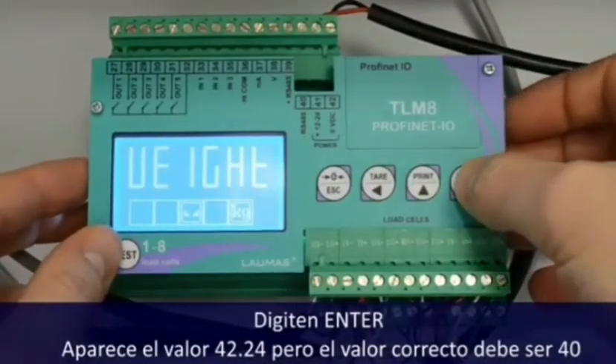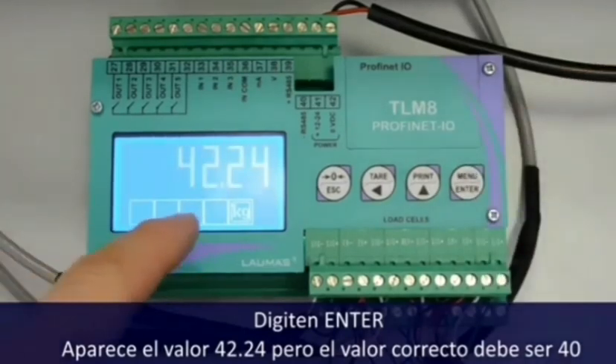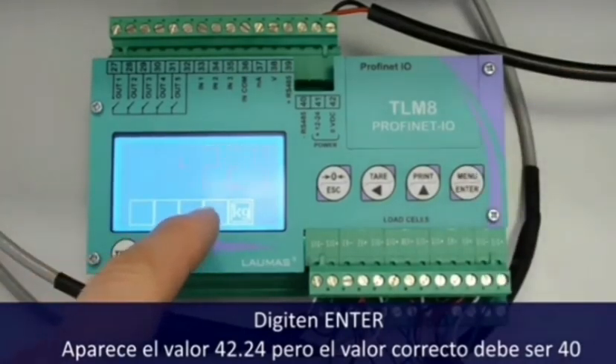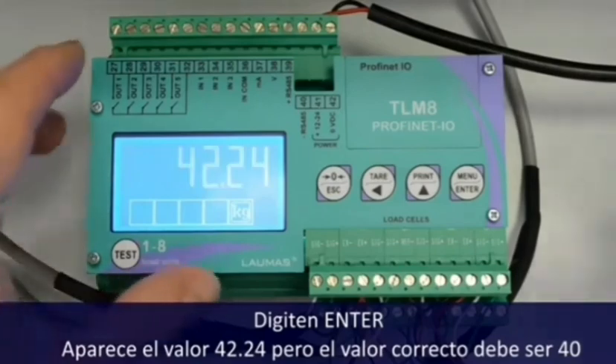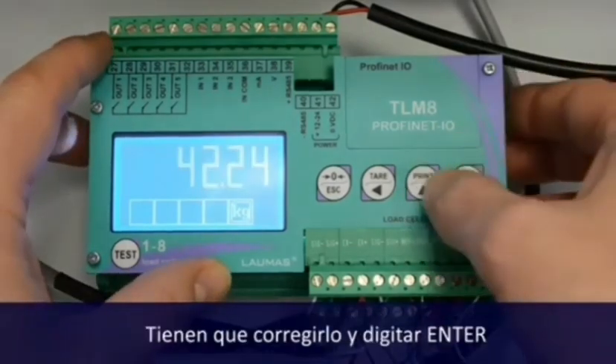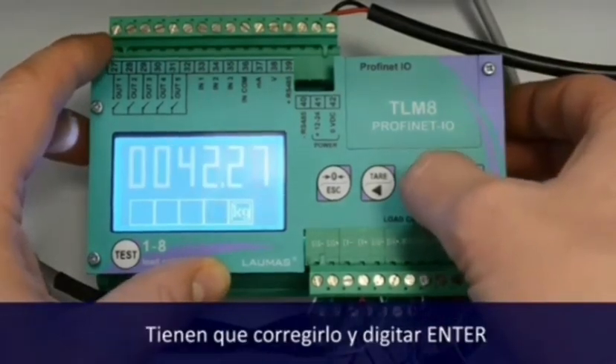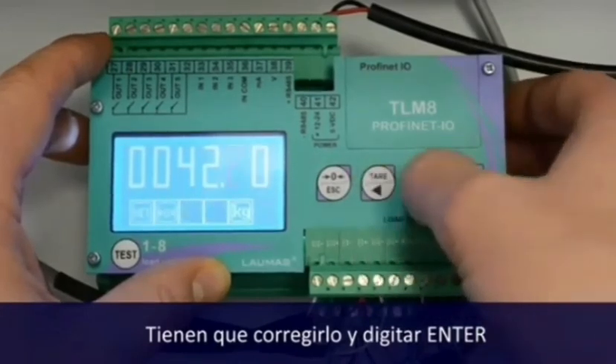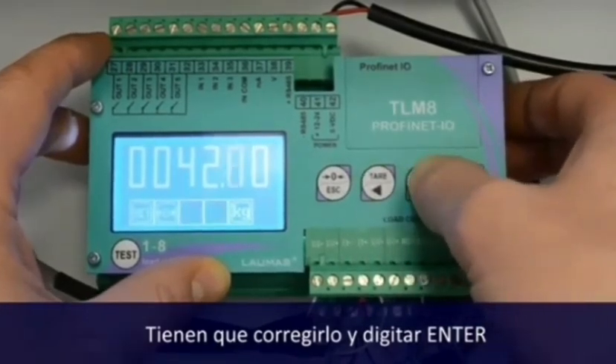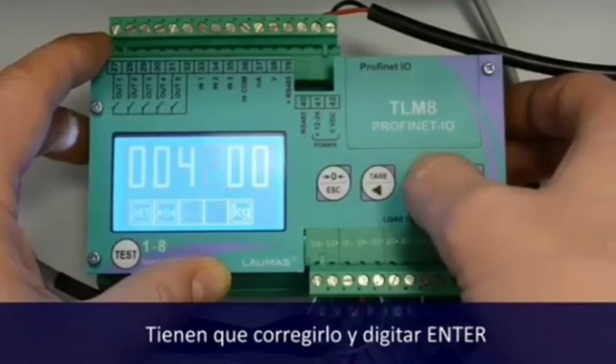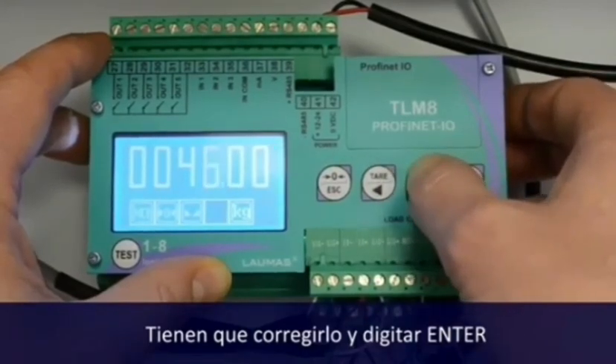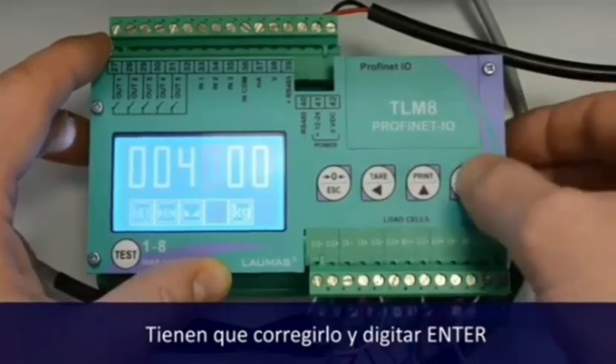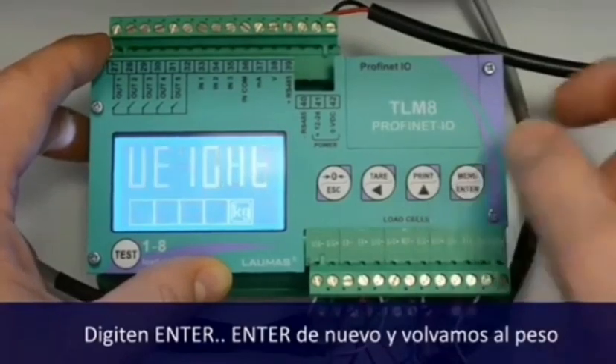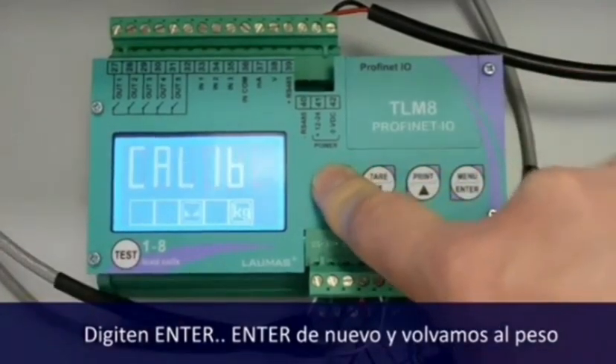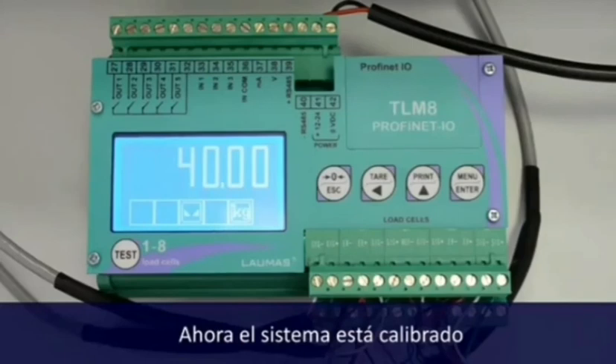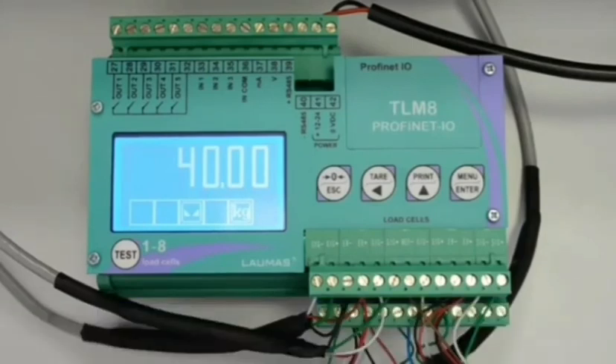Okay, press enter. You see 42 dot something, but we know it must be 40, and so we correct it. Enter, enter again, and back to the weight. Okay, it's done, the system is calibrated.